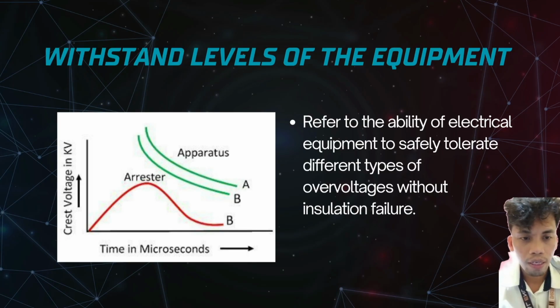For that diagram, it shows how a surge arrestor protects electrical equipment by keeping voltage surge at a level equipment can handle. So visualize the protection margin. So the apparatus curve of green, so this is mga represents a withstand level. So maximum voltage the equipment can take before the insulation fails. So mana siya kanang green. So for the arrestor curve, so mana siyang red. So this is represent protective level. So the voltage where surge arrestor kicks in the divert excessive energy to the ground.